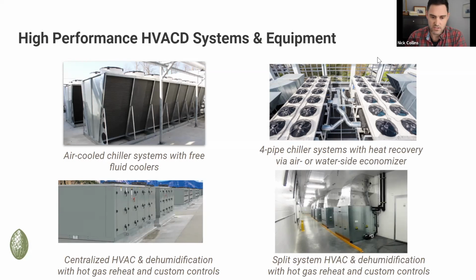What's nice about chillers is that you have a degree of control over the chilled water temperature that you send from the chillers into your process. And that ability to not only change the temperature of the chilled water coming out of the chillers, but also to mix that with hot water, allows you to really dial in the supply air conditions that are being delivered to your space. So a typical direct expansion rooftop unit is really just going to deliver the air to your space under essentially one condition. With a chiller system, you have the ability to really dial in what you are delivering to the space. Chillers also provide the opportunity for free cooling.